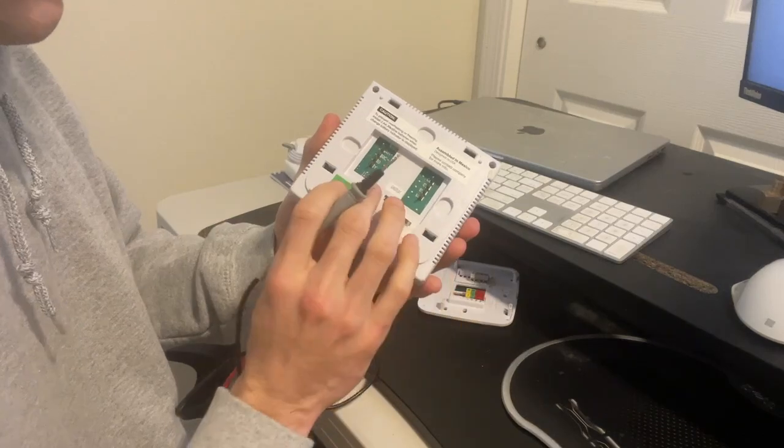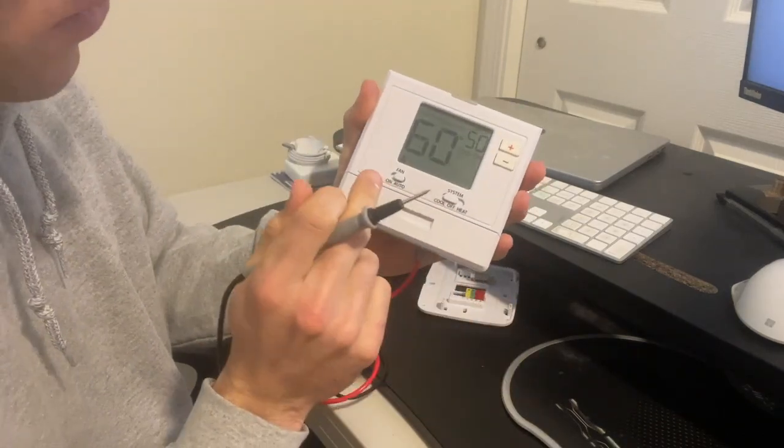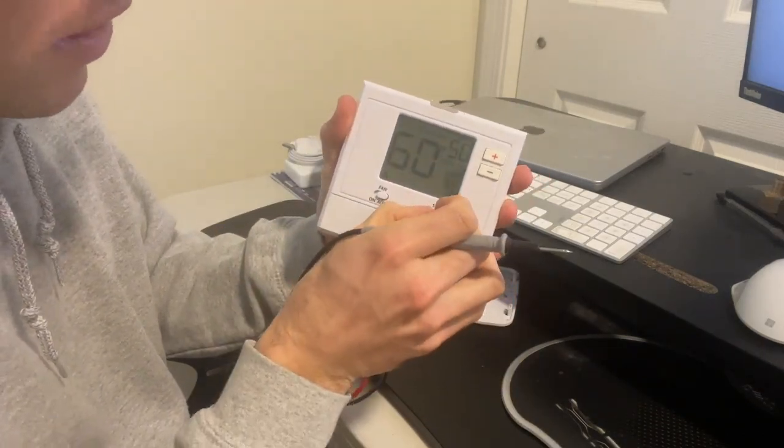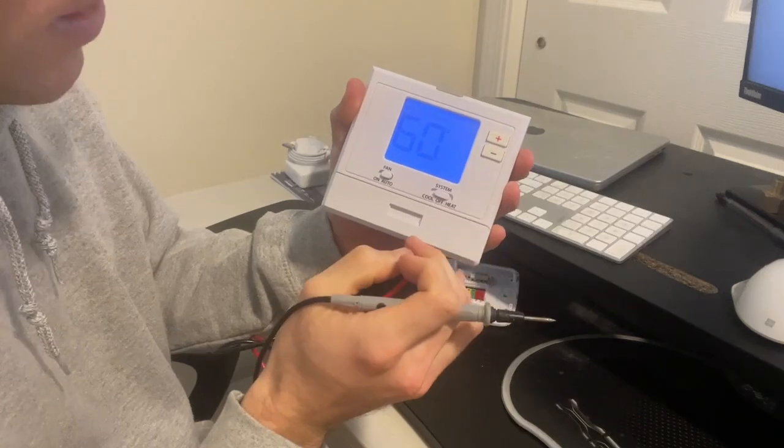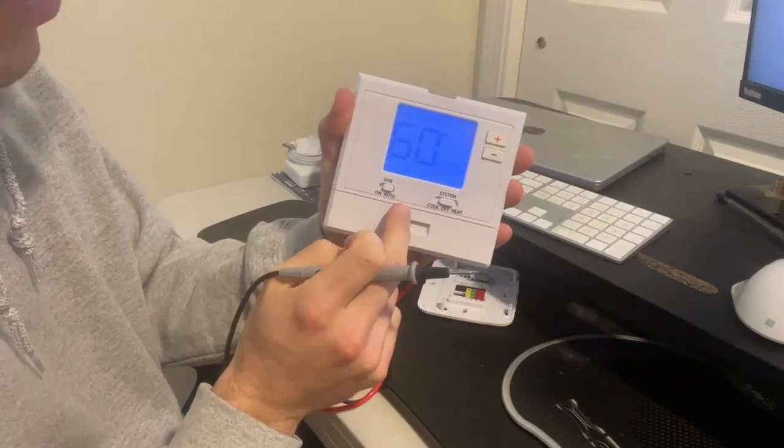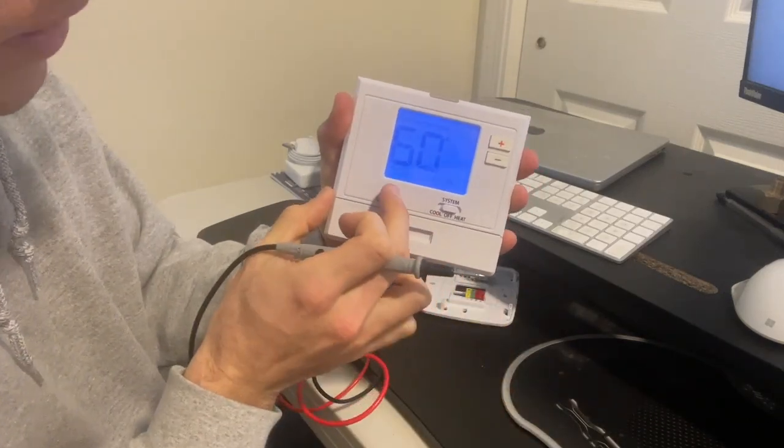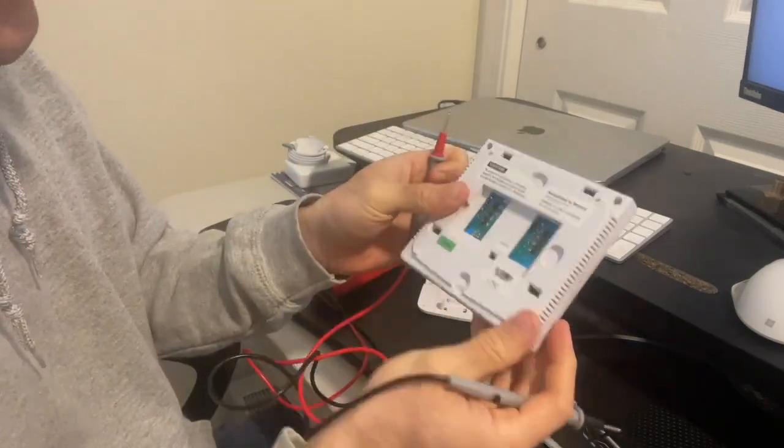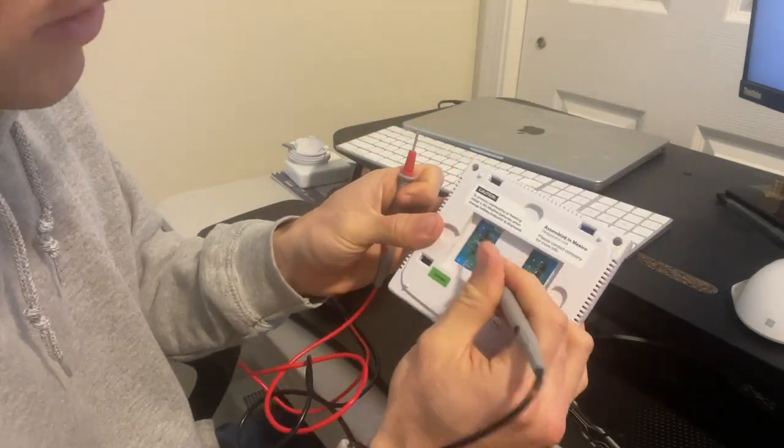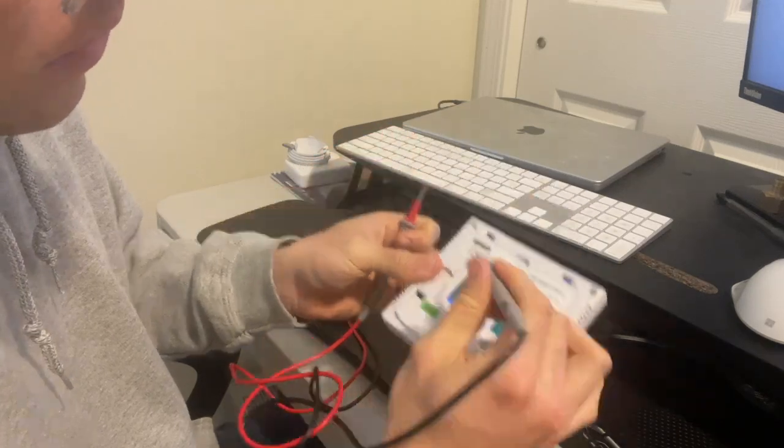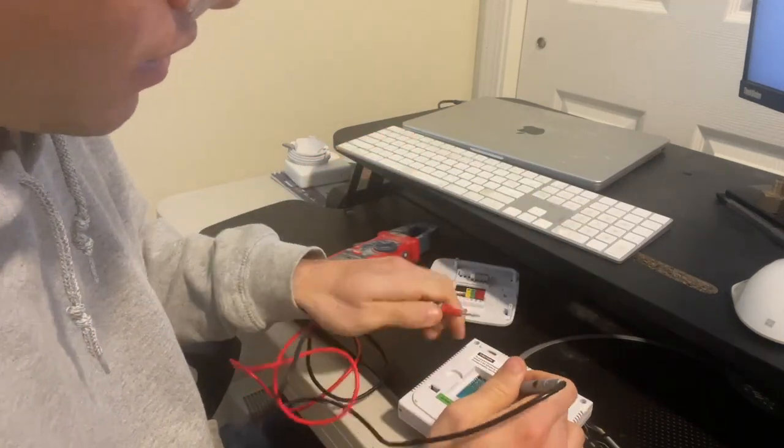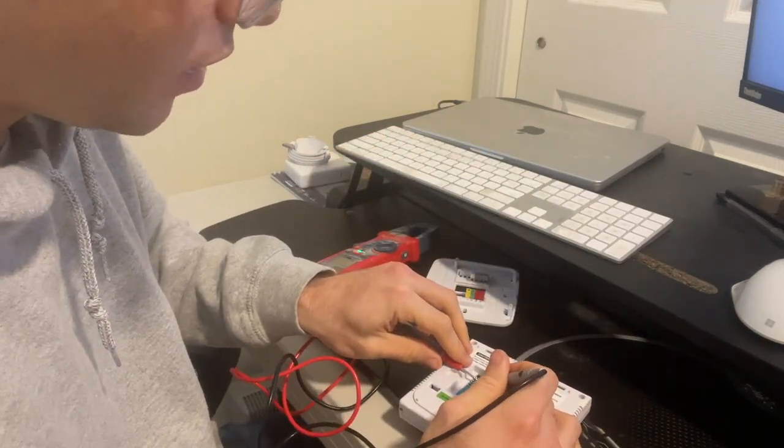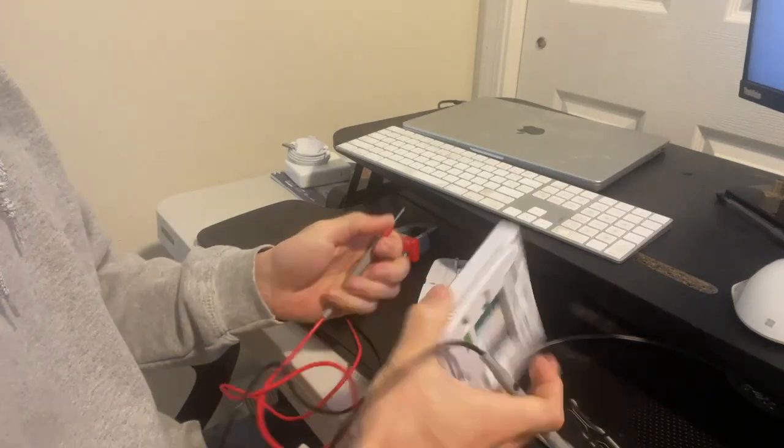And then the final thing you can check is for the fan. So I'm going to set my system to off right now. And if I wanted to just run the fan at my house, I would turn the fan to the on position. And in this situation, I would expect there to be continuity to this G wire right here and to RC, and I'm hearing that, which is good.